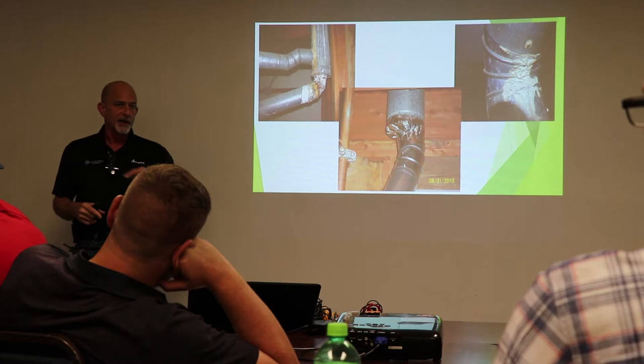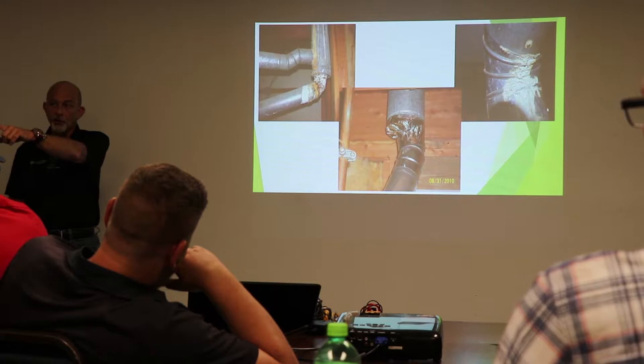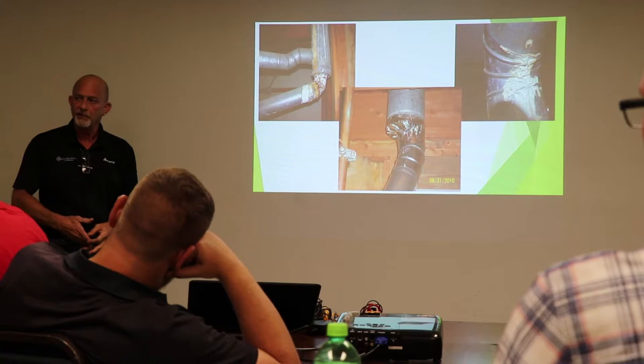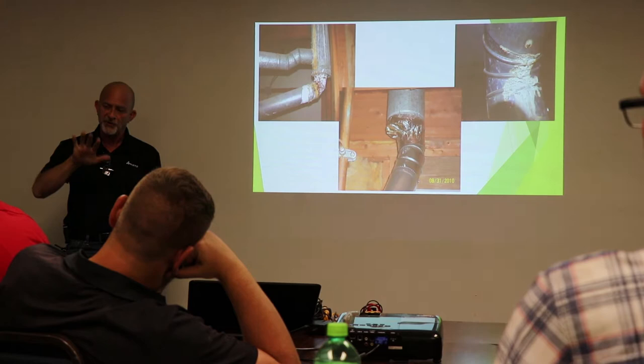Can anybody tell me how much it's supposed to be pitched? Quarter inch per 10 foot. Quarter inch per foot. Per foot. And it should be strapped how often? 2 to 3 feet. Most manufacturers say up to 5. Personally, I go every 3.